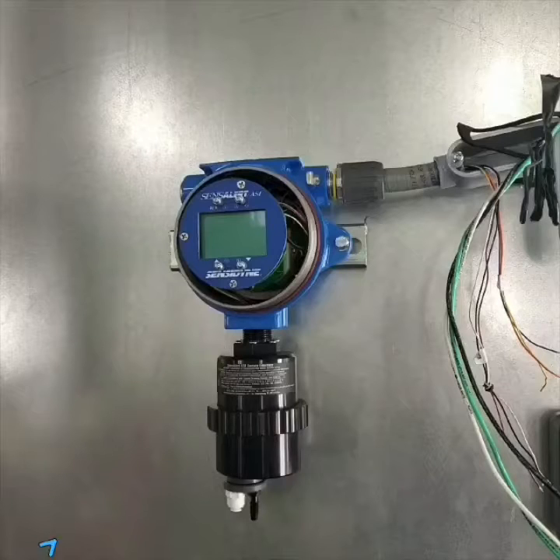This piece right here is temporary and is only going to be used right now. Once we get this powered up, we will use this to calibrate the sensor. We will use a methane mixed with oxygen and nitrogen — the combination of the three is very precise and gives the same properties as if there were ethanol being sensed.